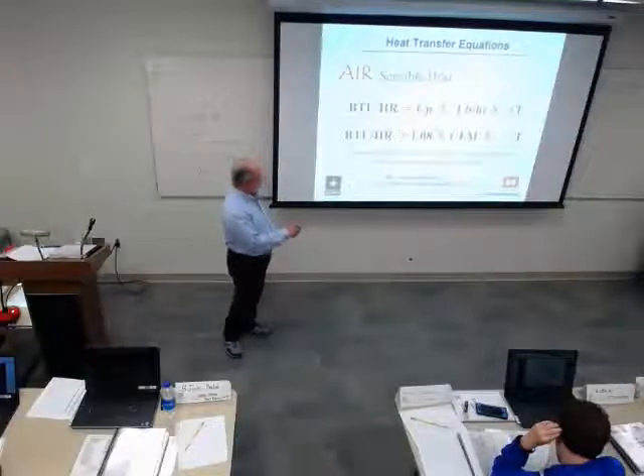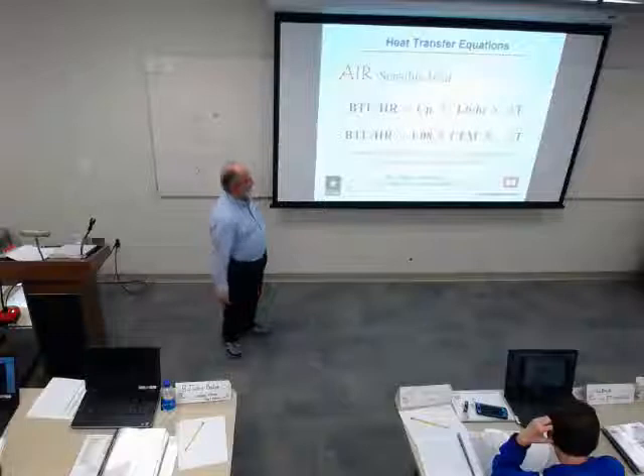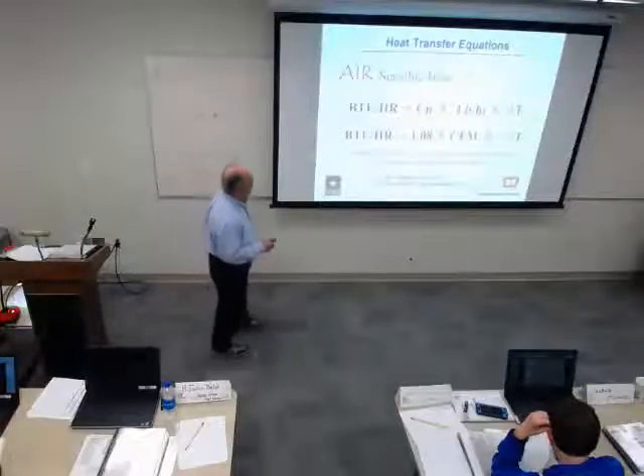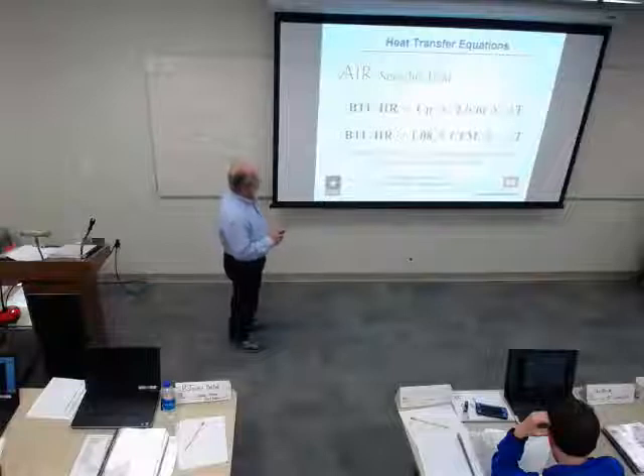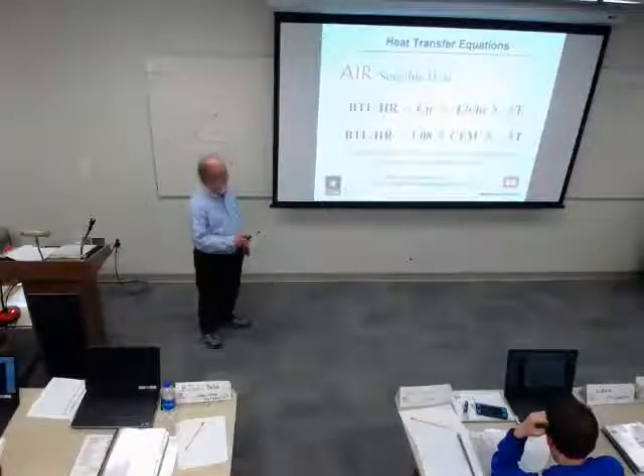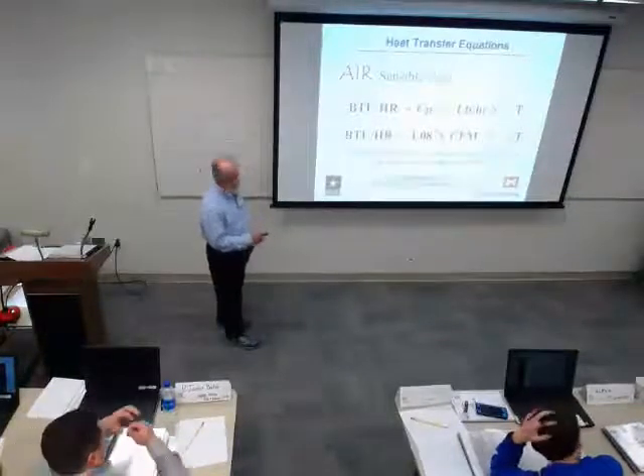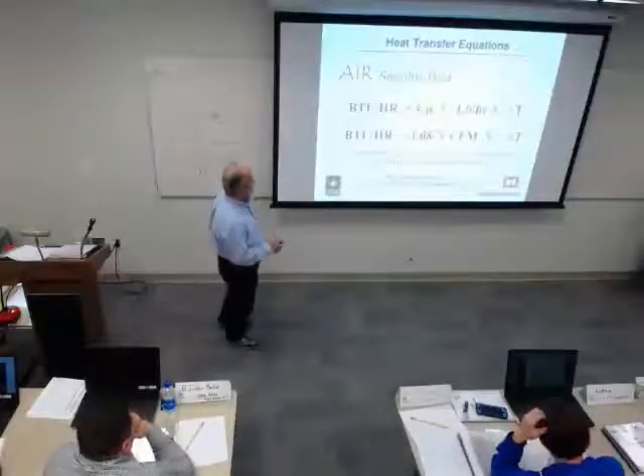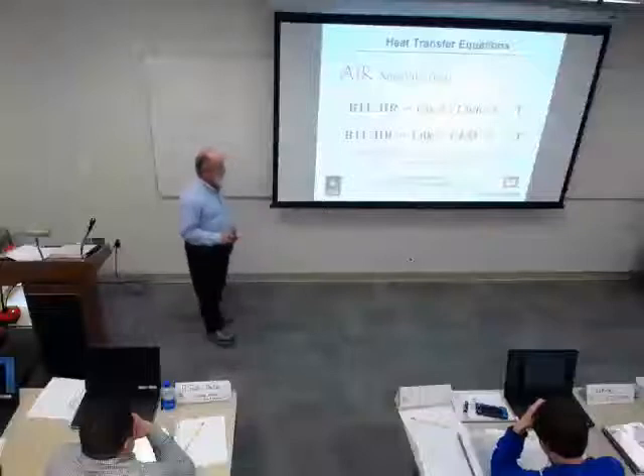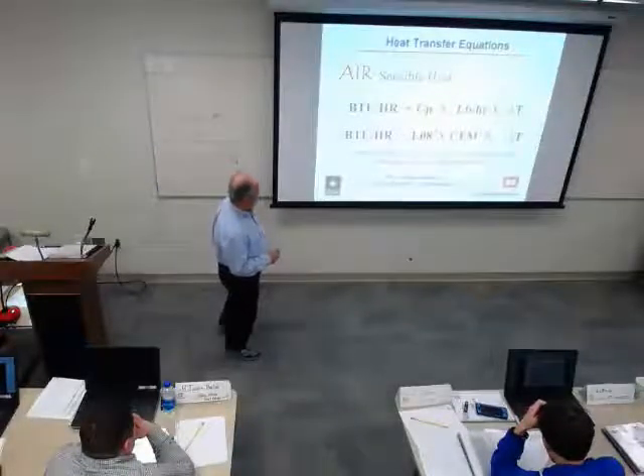So sensible heat for air, in BTUs per hour, is equal to the specific heat, C sub P, times the pounds per hour times the change in temperature. Right now, don't worry about pounds per hour because we'll put it together. But if you're doing it on a mass basis, that's how you do it. BTUs per hour are also equal to 1.08 times CFM times the change in temperature. This is the one you see the most often. The first one is a little bit more accurate if you come up with the pounds per hour, but because of the way our measurements are made, this is the one you're going to see most often. The constant includes the specific heat for air and water vapor, density, and a correction at standard conditions. Forget the time bit.